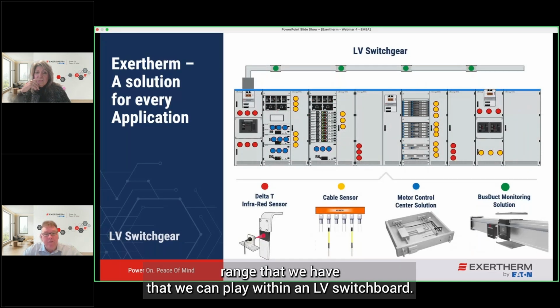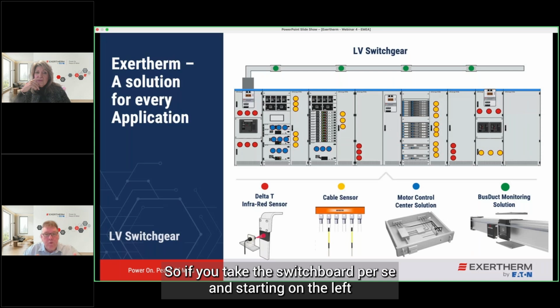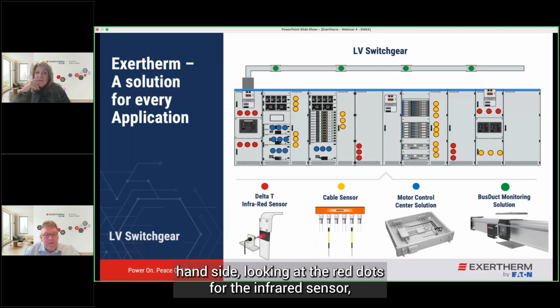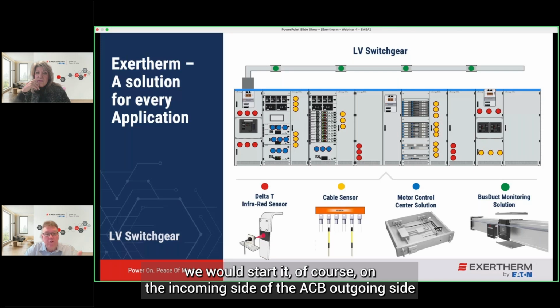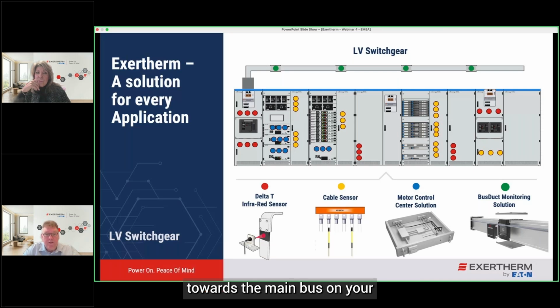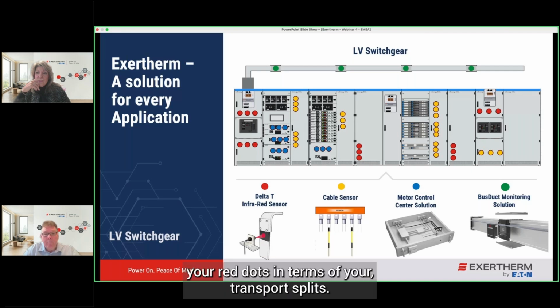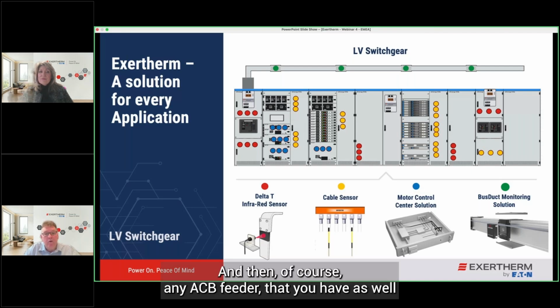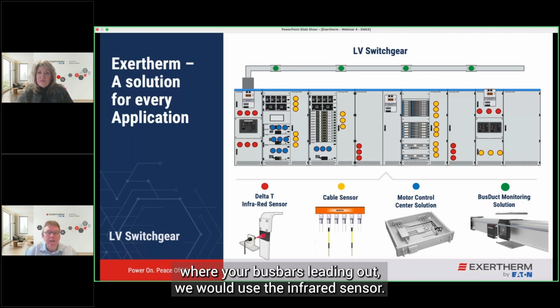can play with in an LV switchboard. So if you take this switchboard per se, starting on the left-hand side, looking at the red dots for the infrared sensor, we would start, of course, on the incoming side of the ACB, the outgoing side towards the main bus, on your red dots in terms of your transport splits, and then any ACB feeder that you have as well, where you have bus bars leading out, we would use the infrared sensor.